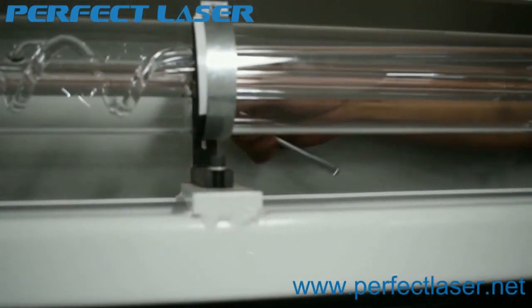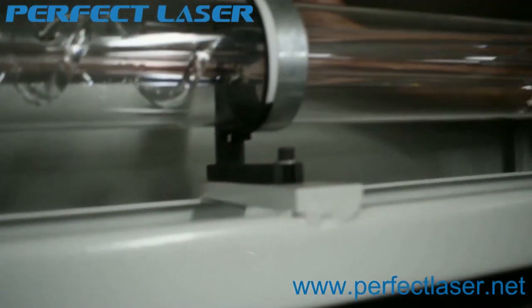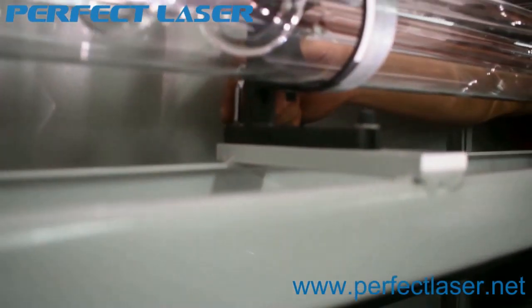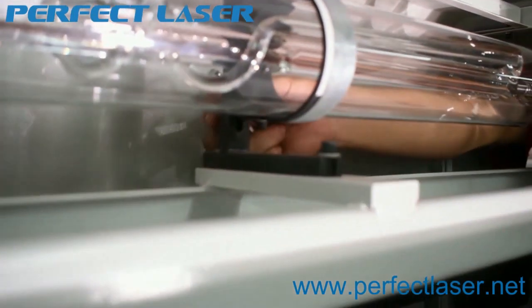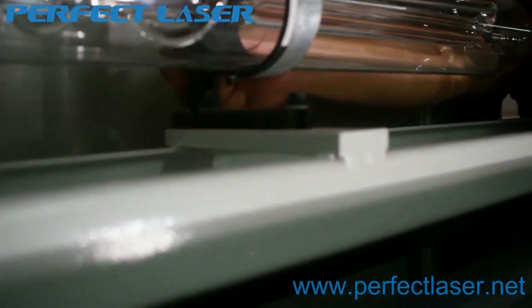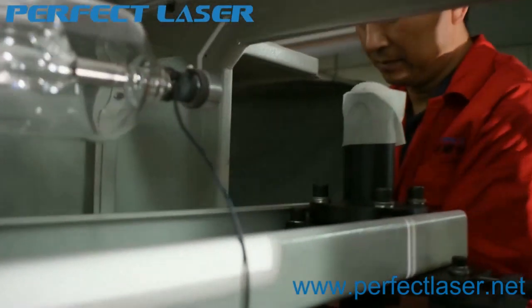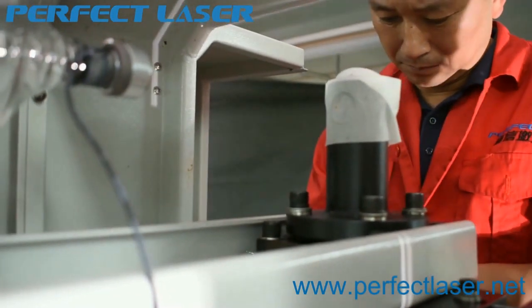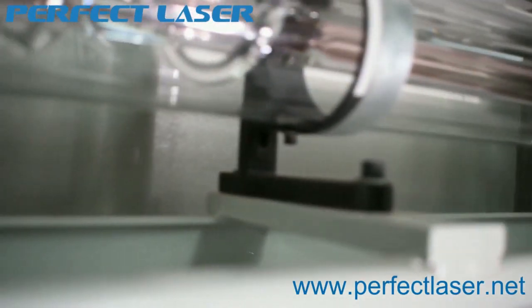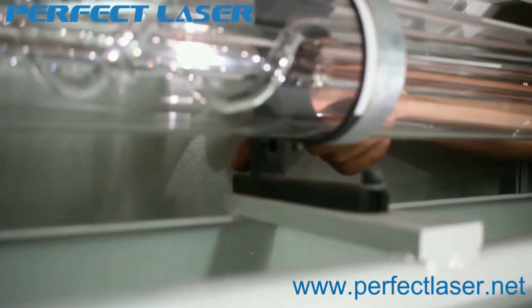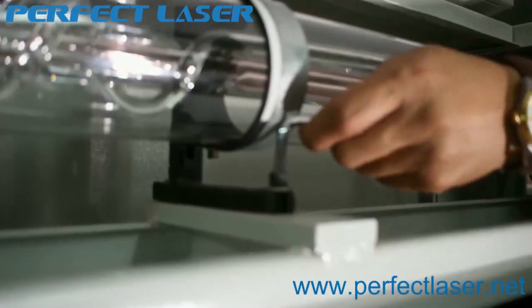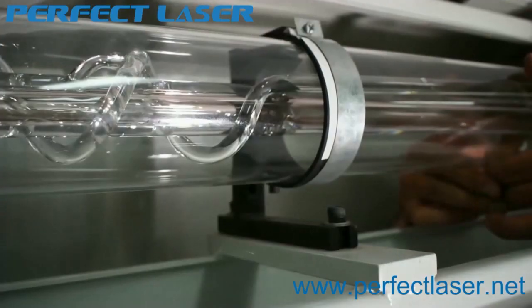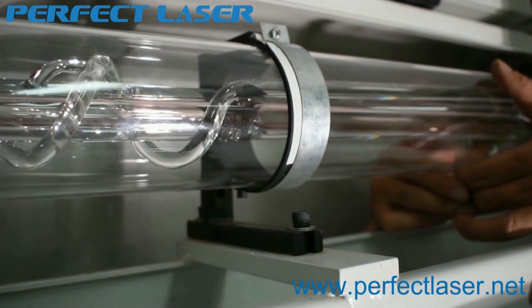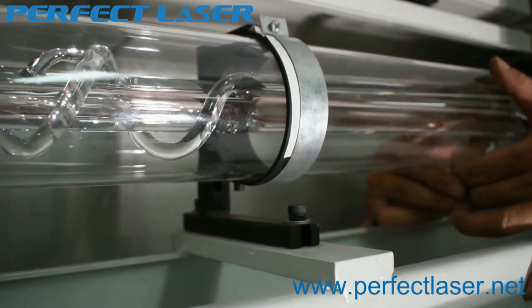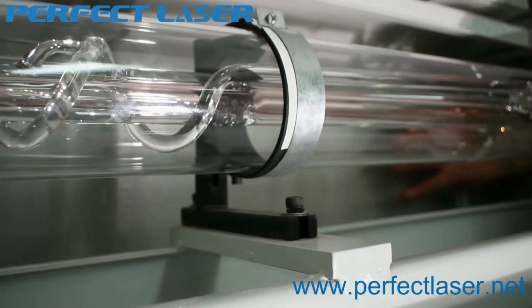So we align the laser beam holder. There are 2 screws in the laser beam holder. When the laser dot is in the left, we have to align the laser beam holder. Loosen the screw in the 2 sides of the holder, and move the laser tube into the right position.